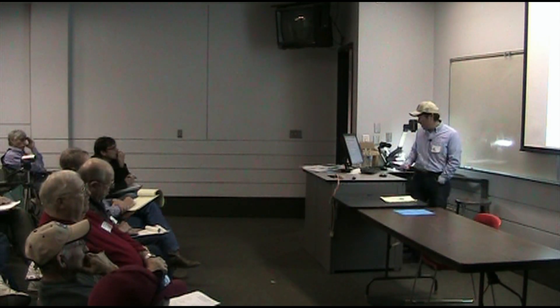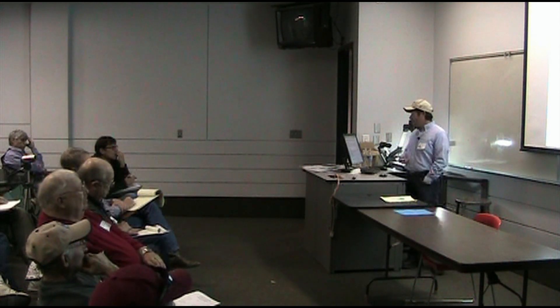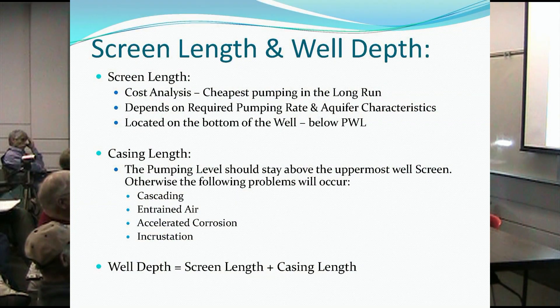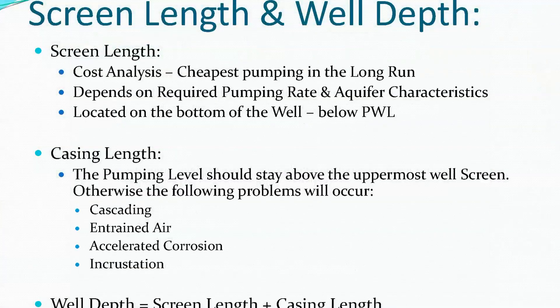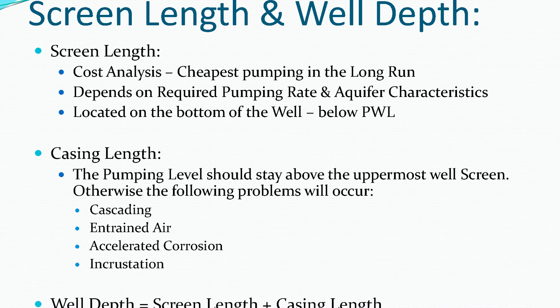How much screen do we need? What I do is a cost analysis — we look for the cheapest pumping in the long run, so over 10 or 20 years. We design based on long-run cost, which depends on how much we're pumping and on the aquifer characteristics. The screen is located at the bottom of the well, below the pumping water level.